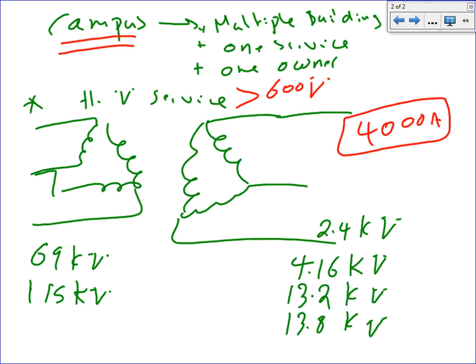Look at what they're doing here on the secondary side. Most of the time, it comes delta delta. Most of the time, look at the primary. If you go to UVM, they have a high voltage substation. On the primary side, look at the voltage that they're bringing to the transformer: 69 kV. That's a high voltage. Or 115 kV. These are your primary. Look at your secondary side.